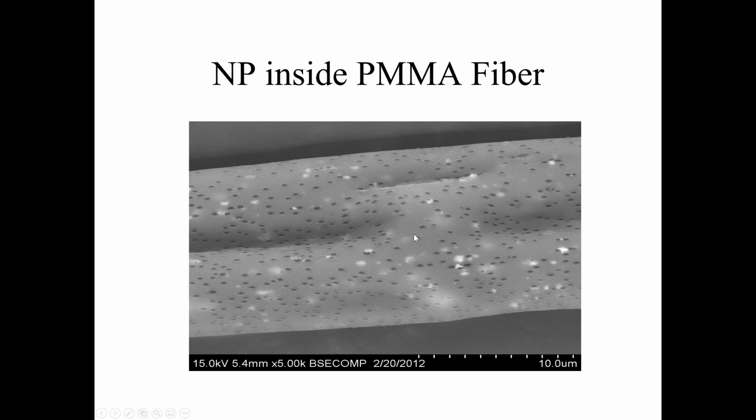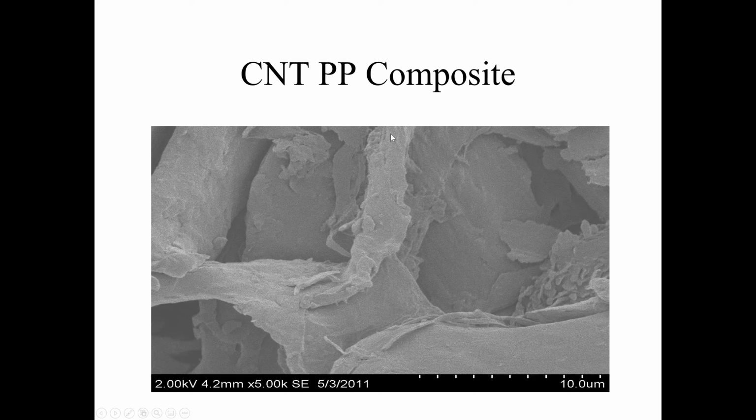It's a backscatter image. These are carbon nanotubes, polypropylene. If I had a TEM, or if I had an instrument that had a field emission gun, you would see these as individual fibers, but that's one of the limitations of the tungsten filament that's in this microscope. It's also why the price is $100 grand, not $1 million. This is a commercial carbon nanotube that was bought.